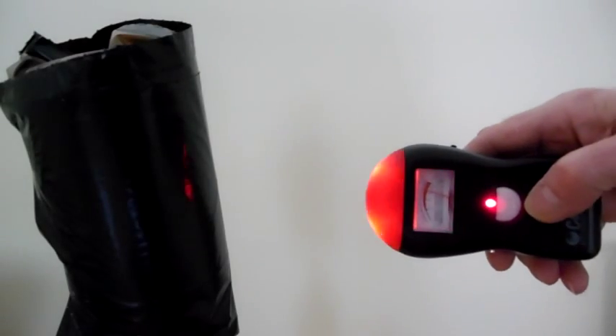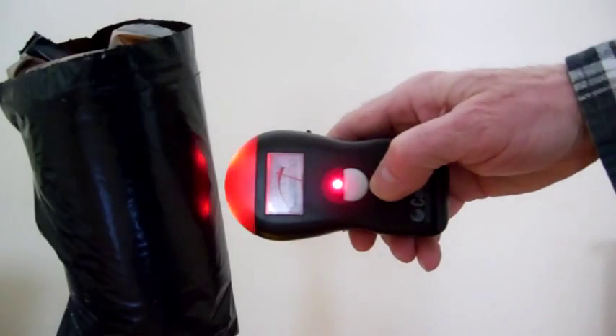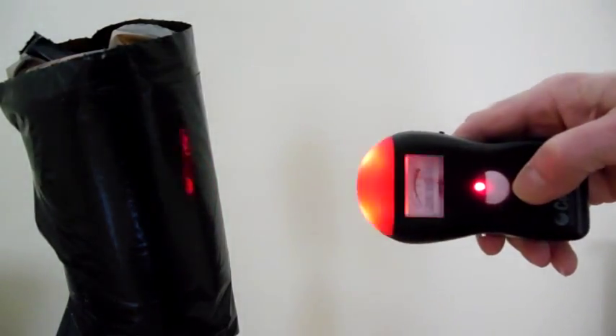The reason for covering the lamp with a black plastic container is so that the camera can distinguish the flickering light of the field strength meter. The light flickers in conjunction with the field intensity, as you can see by the moving needle on the meter. The passive antenna circuit that I am using picks up a broad spectrum of radio frequency energy. It is approximately 4 feet away from the lamp and uses no amplification of any sort. What you see on the oscilloscope is what you are being exposed to.